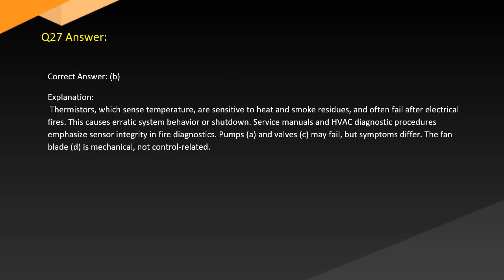Answer. Correct answer: B. Explanation: Thermistors, which sense temperature, are sensitive to heat and smoke residues and often fail after electrical fires. This causes erratic system behavior or shutdown. Service manuals and HVAC diagnostic procedures emphasize sensor integrity in fire diagnostics. Pumps (A) and valves (C) may fail, but symptoms differ. The fan blade (D) is mechanical, not control related.